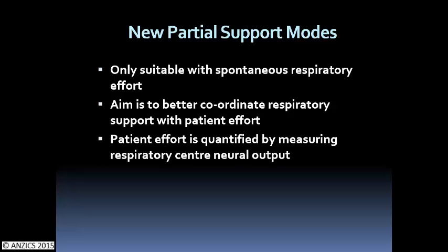So having the triggering system change from pressure to flow, and then putting the flow sensor right at the Y piece, was a really good thing for us in small kids, because it made the ventilator much more sensitive to patient effort to breathe. The problem still is that if there's a leak around the tube, or a patient is making very weak efforts or can only generate very small flows, the ventilator still won't trigger.